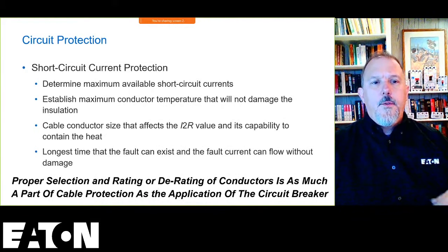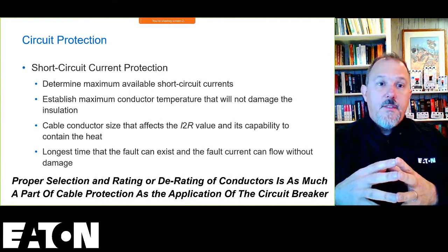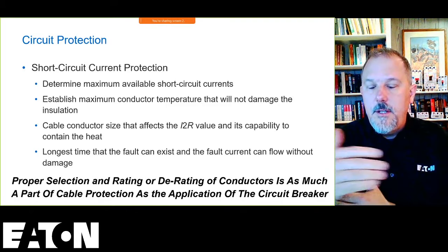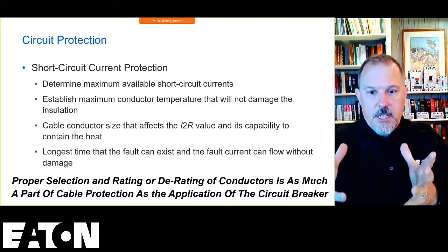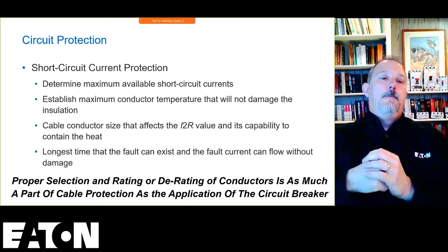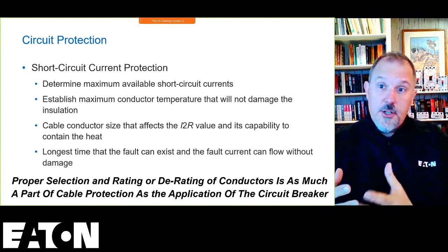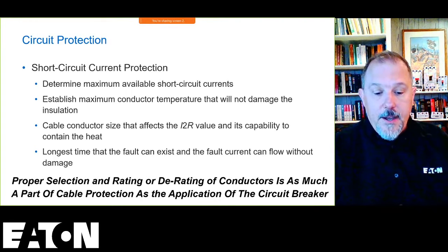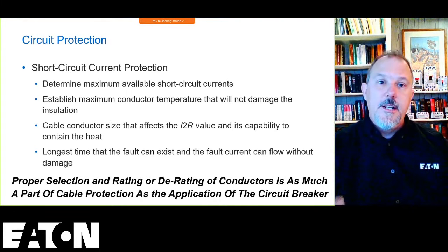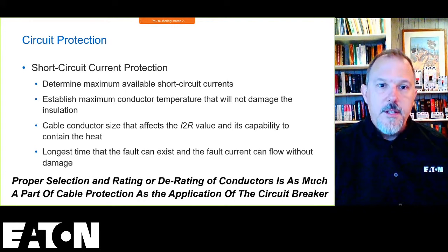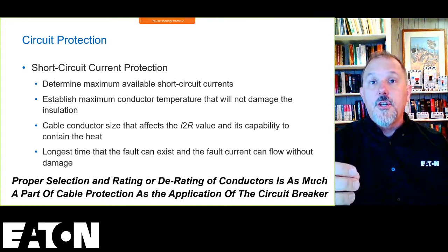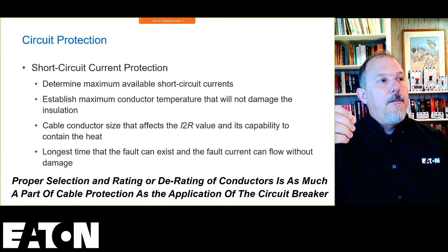So we provide, you have to pick the right conductor, understand the insulation ratings, what can be used in all these different types of environmental conditions that we're going to place them in. Another thing that we have to think about is short circuit protection. To evaluate a conductor for short circuit protection, I have to understand the short circuit currents. I have to understand the capabilities of the conductor from a short circuit current rating perspective.